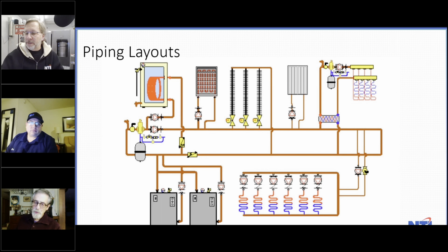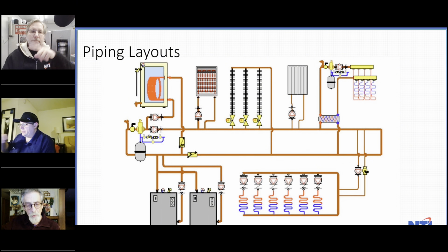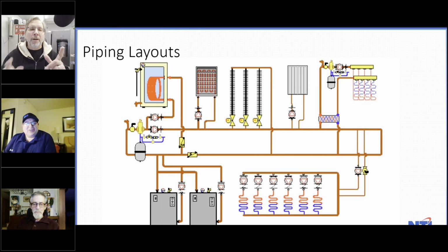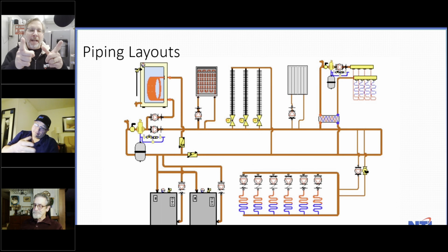Well, what I always used to do, I never used an Axiom pump. That's kind of a newer thing for me. But what we used to do is we'd pre-mix everything in a barrel like a trash can, and then we would pump out of the trash can into the system, bring on another hose back from the system, which you drop to the bottom of the barrel. That way you fill the system, and when you don't see any more bubbles coming back, you've properly purged the entire system. Yeah. People would ask why you have those 2 draw-offs with a valve in between, right? So you could have the supply and return going out and have them separated.